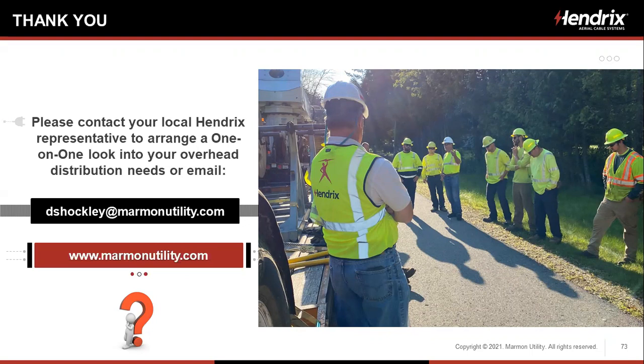Thank you. Next one, is galloping an issue? And if so, do you recommend the use of dampers? Okay, so when we talk about spacer cable, I know that there's a video out there showing spacer cable galloping. I cannot explain it. This happened decades ago, and we've got over 500,000 miles of spacer cable. We've never had a galloping related failure. When we use spacer cable, we essentially have a vibration damper every 30 feet, right up to 69 kV. With 115 kV, we're going to have a vibration damper every 50 feet.